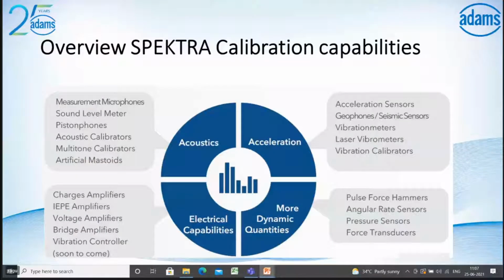Portfolio calibration capabilities. Spectra is offering different calibration solutions, such as acceleration and shock calibration systems. What sensors can be calibrated? Vibration sensors such as ICP, charge, voltage, MEMS type and piezoresistive sensors, and low frequency sensors such as seismic sensors, vibration meters and vibration calibrators.